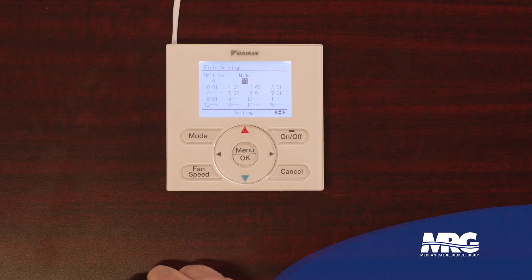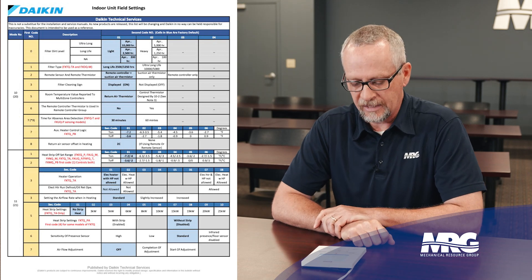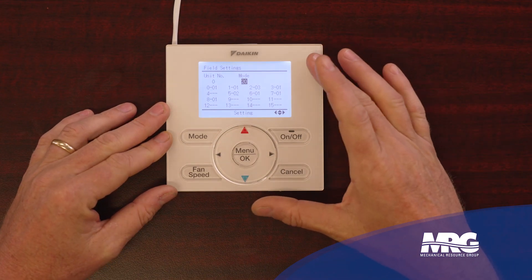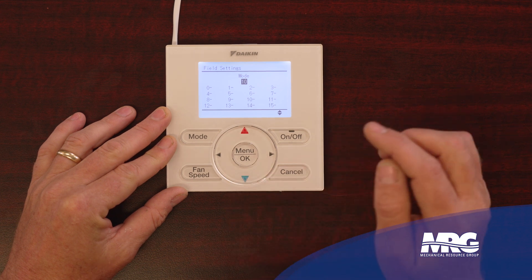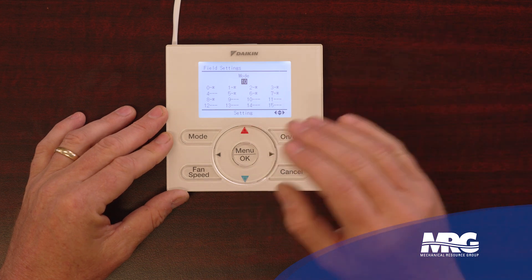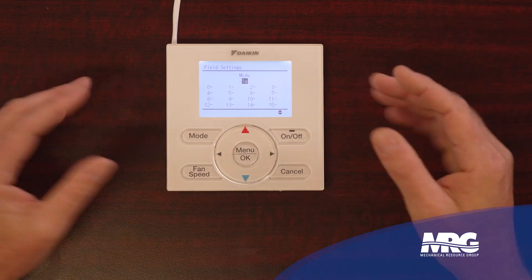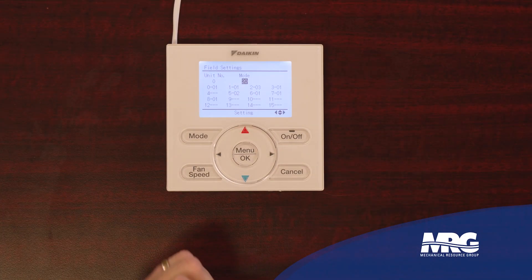Now the next option here — mode 20 — that's my service setting mode I'm in. As you see when I scroll up, that changes to mode 21. One thing to remember: when you look at your field settings table, you'll see a mode 10 and then maybe a 20 in parentheses. Mode 10 would be if I wanted to make this change to the entire group of indoor units — assuming I've got multiple indoor units on this one stat and I wanted to make the same change across the board. If I use mode 10 with multiple indoor units, I'd make the same change to all of them. It seems a little counterintuitive — like the lower number might be for the single unit and the higher number for the group — but it doesn't work that way. The higher number, mode 20, is for the single unit, and mode 10 is for the group. We have a one-to-one setup, so we're going to use mode 20.